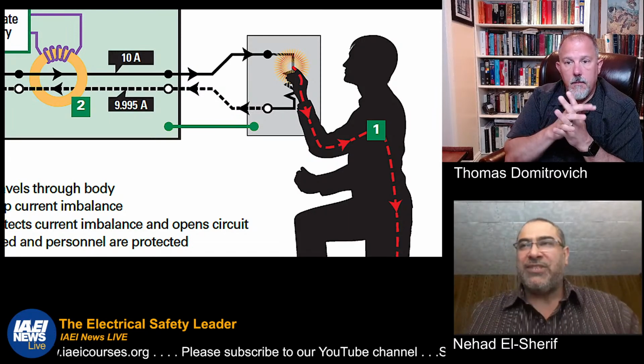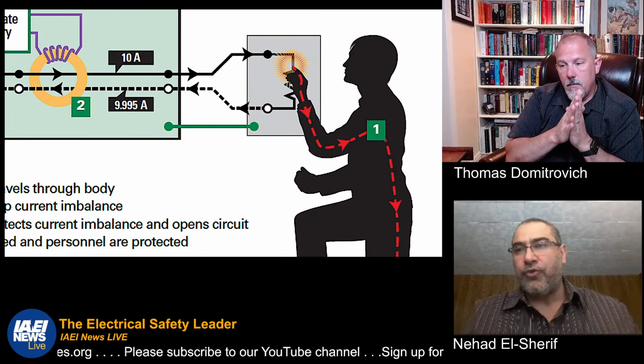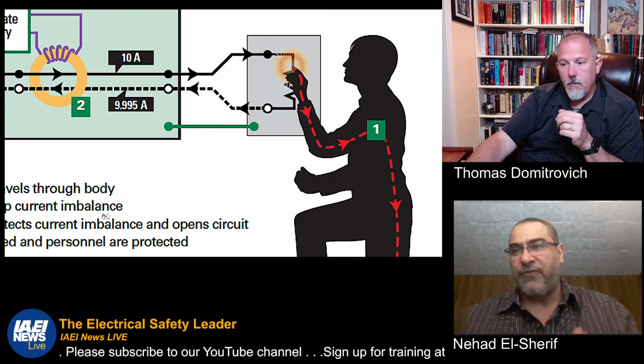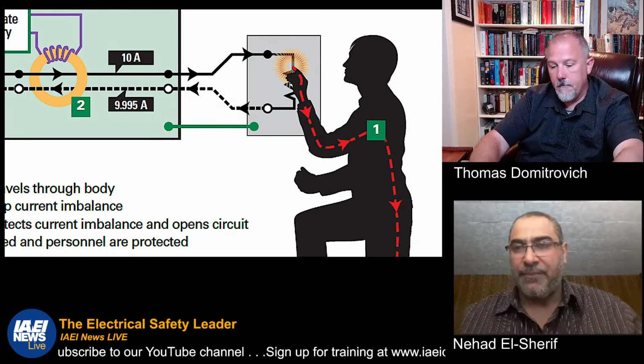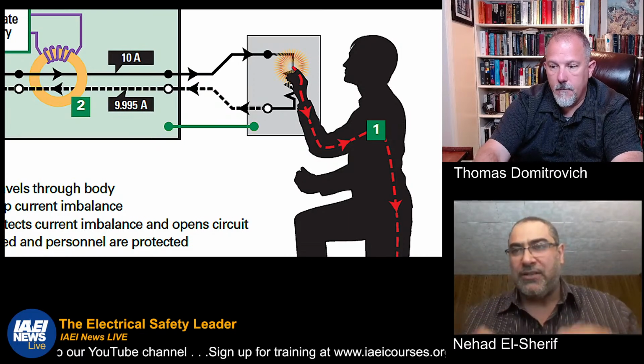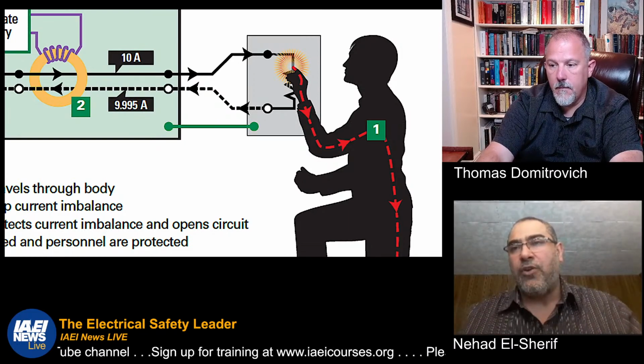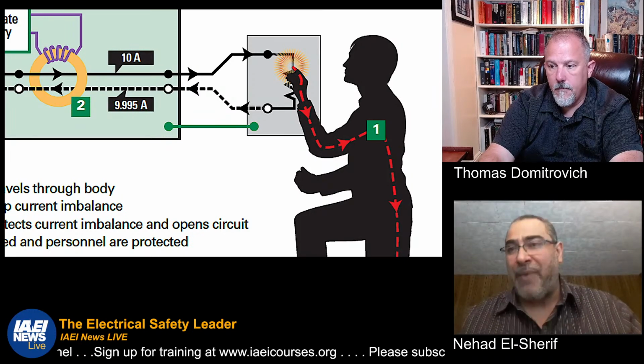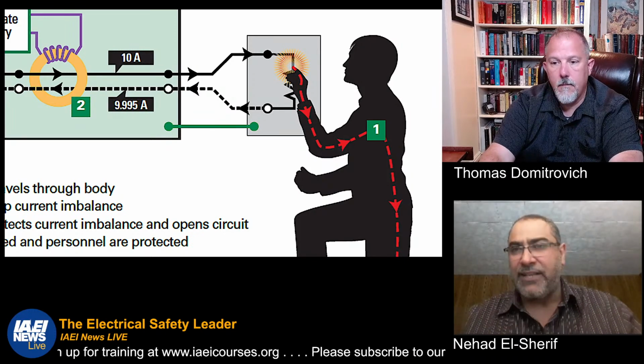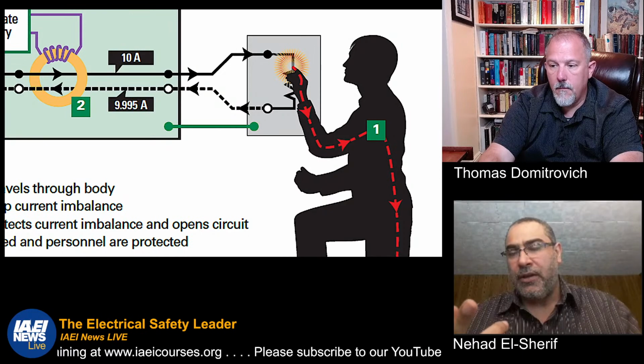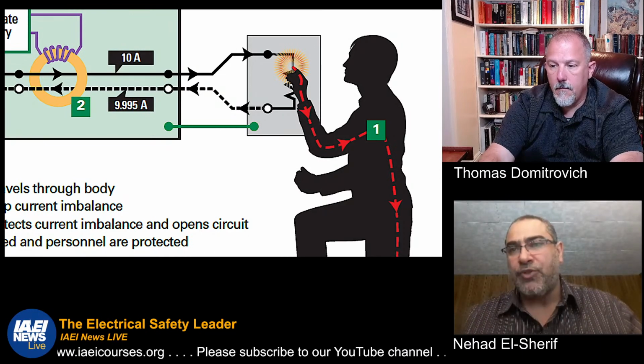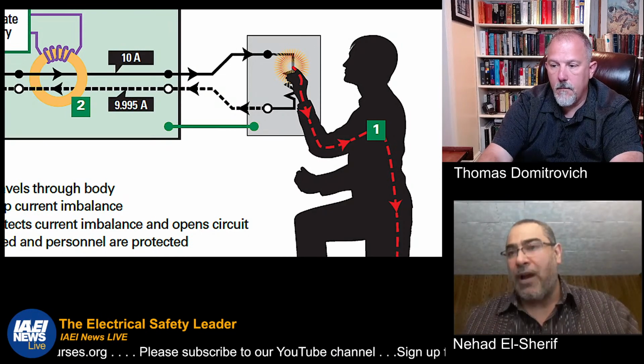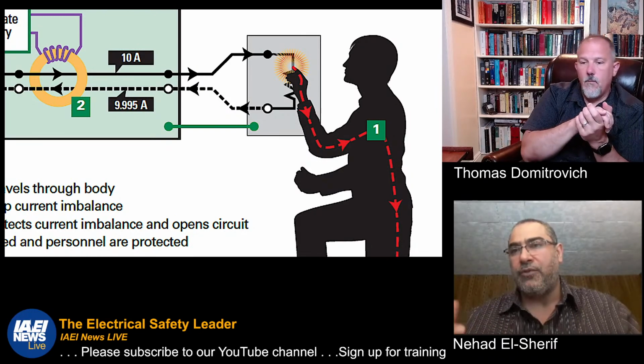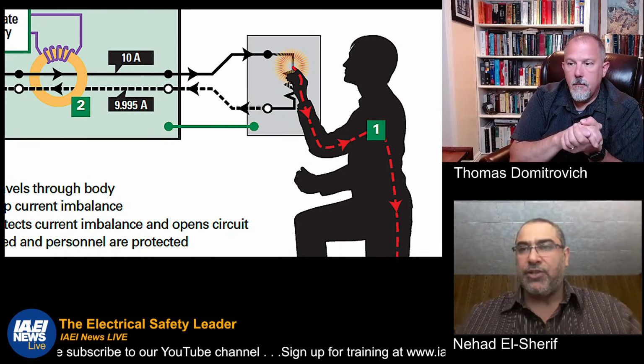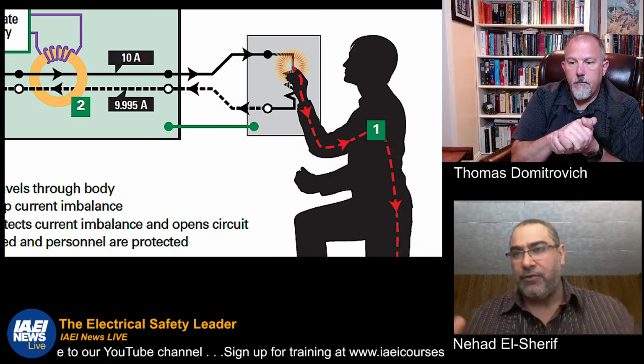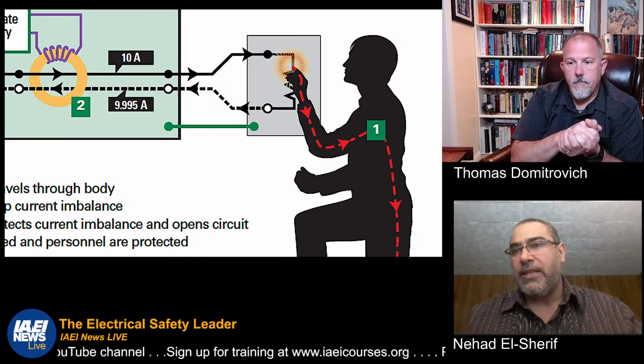So maybe 90%, 95% of your electrons would go through the path of least resistance, but then you have this 5%, maybe 2%, whatever the percentage is, depending on the ratio of the impedance, that will be going through the alternative path to get to the source. And this is where the problem is. Like Tom is showing, if there is a path through ground, the equipment ground, the conductor connected to ground, or the ground mat or whatever, back to the source, the electrons could take it.